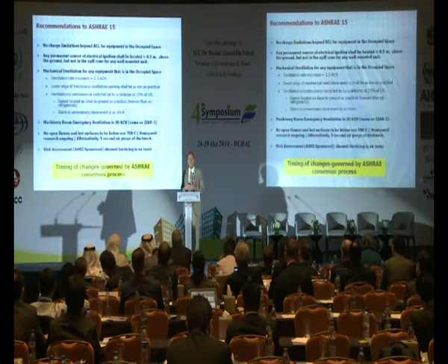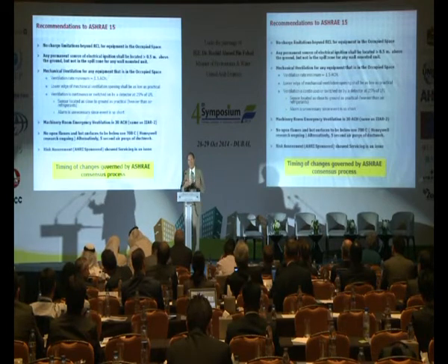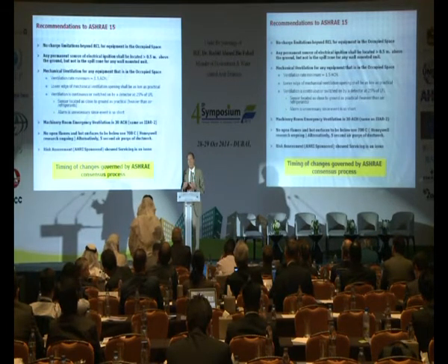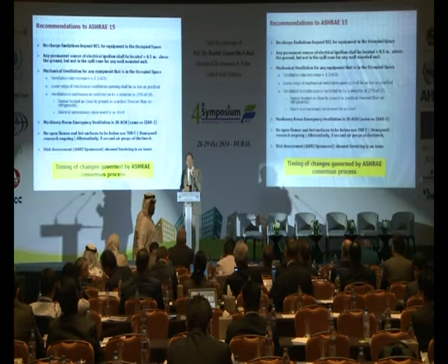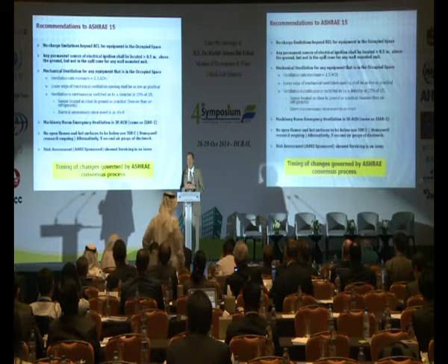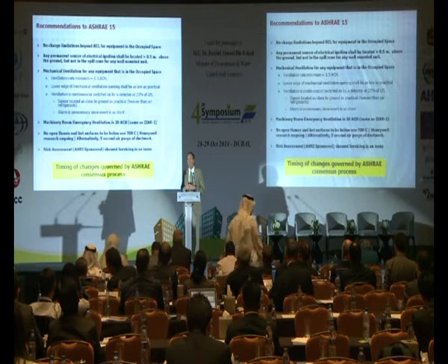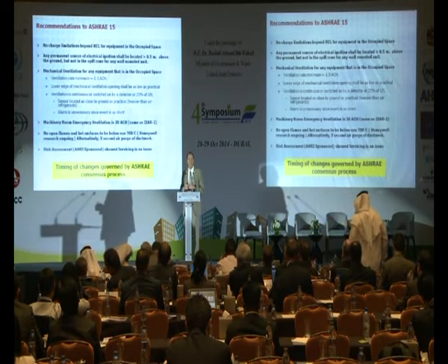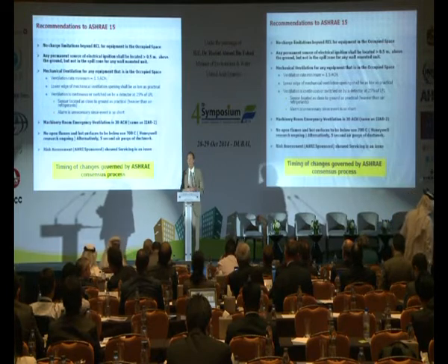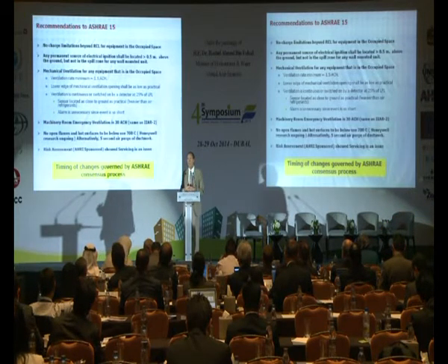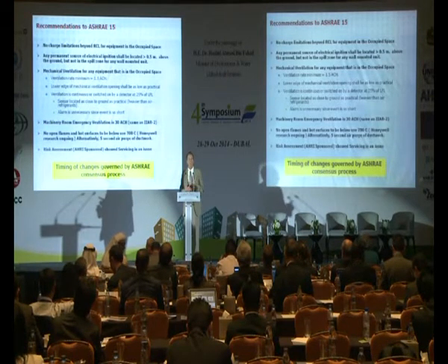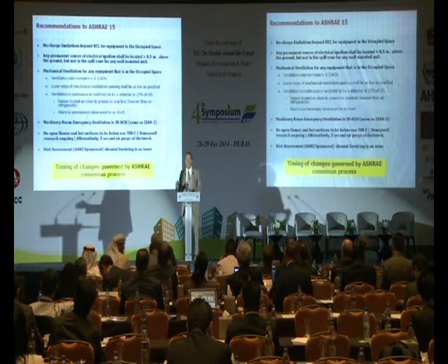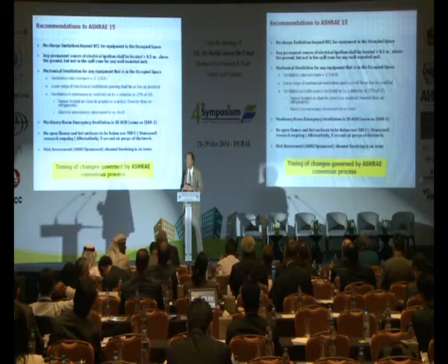The failure to do the things that you need to do to really get service technicians in the place they need to be for the unusual things that they're going to be asked to do with this equipment, that's real. So I would tell you there's one thing, and above all other things, that manufacturers and regulators need to think about in terms of service, and that's warn people that this is new, different, and unique. Okay, don't hide from the fact that whatever refrigerant you're putting in this isn't an A1 refrigerant anymore. It's something else, and you better think about doing things differently. Failure to warn, the number one problem. Okay, put big labels on things. Let them know it's new and different and unique.